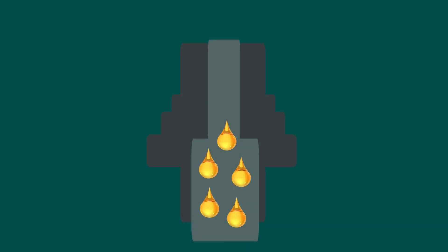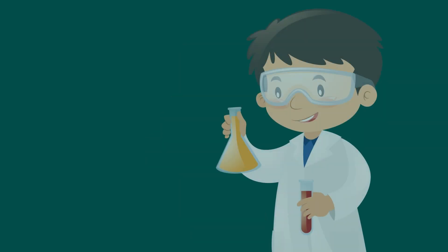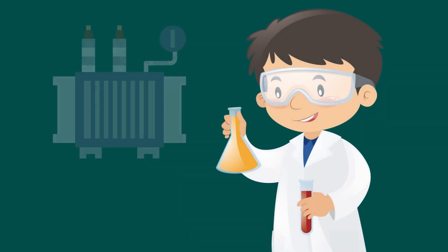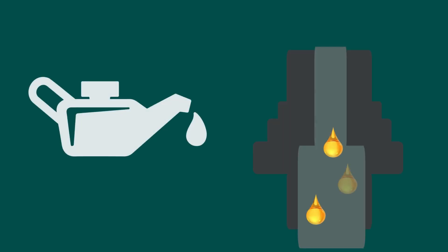However, during operation, the volume of oil in a high voltage bushing may decrease, for example, due to periodic sampling of oil for analysis or a sealing failure. In this case, oil filling is required to regain the oil level so that a high voltage transformer bushing functions properly.